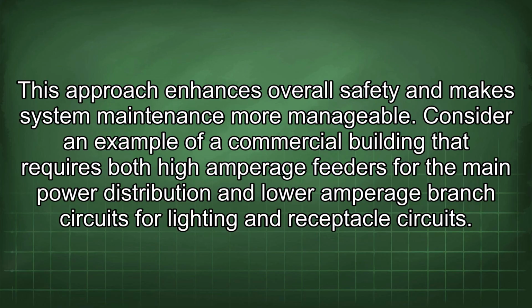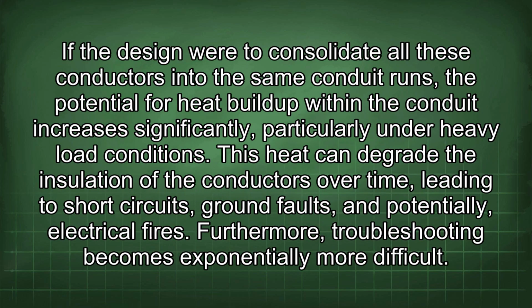Consider an example of a commercial building that requires both high amperage feeders for the main power distribution and lower amperage branch circuits for lighting and receptacle circuits. If the design were to consolidate all these conductors into the same conduit runs, the potential for heat buildup within the conduit increases significantly, particularly under heavy load conditions. This heat can degrade the insulation of the conductors over time, leading to short circuits, ground faults, and potentially electrical fires. Furthermore, troubleshooting becomes exponentially more difficult.